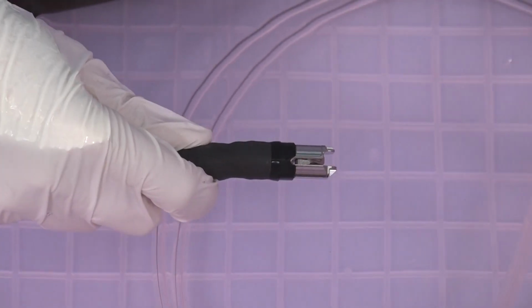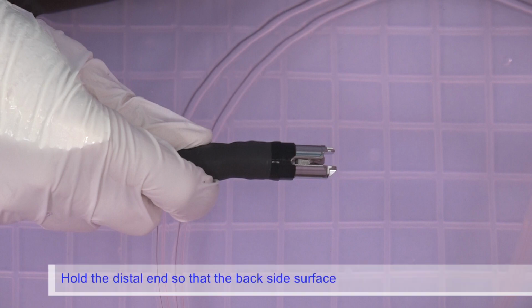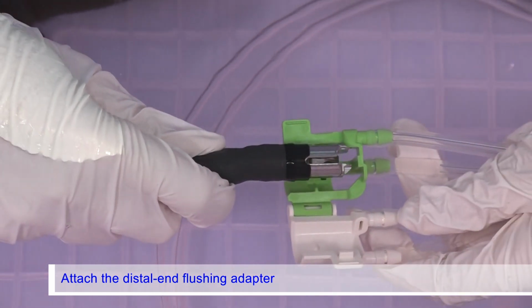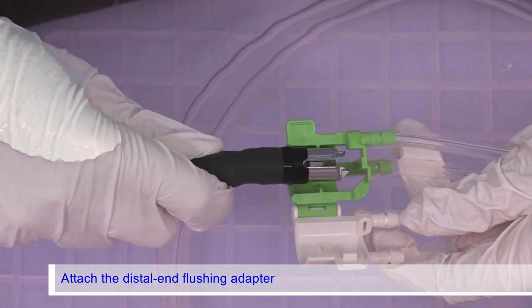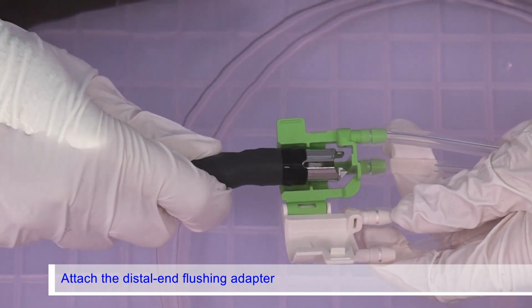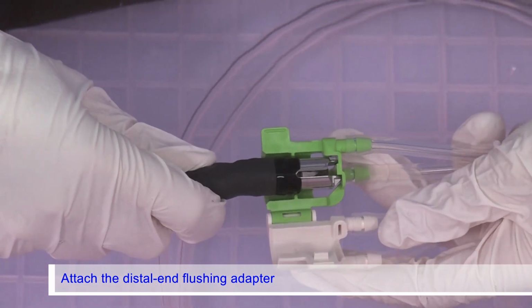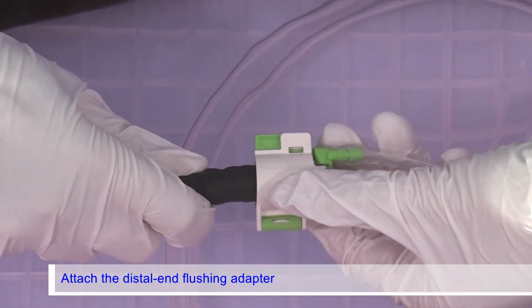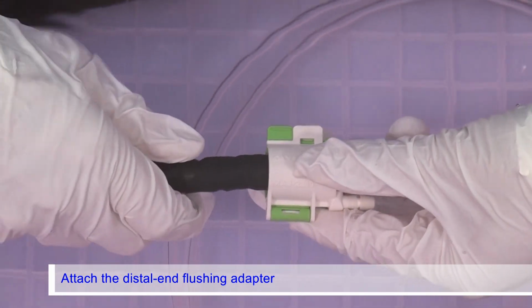For flushing the distal end with disinfectant solution steps, immerse the distal end flushing adapter, a 30 milliliter syringe, and the endoscope in the disinfectant solution completely. Hold the distal end so that the back side surface is viewable. Put the distal end inside the green cover with the back side surface viewable and slide the distal end as shown. Then shut the white cover and the green cover with a snap.